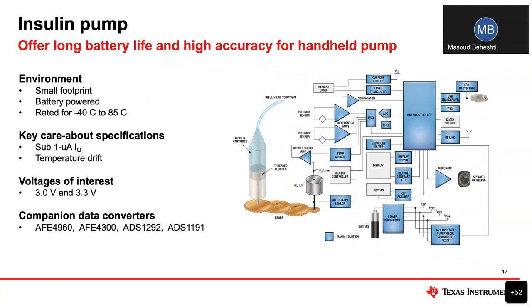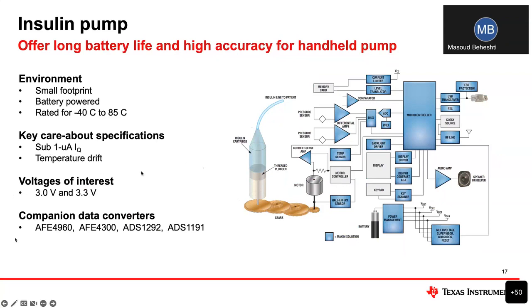Insulin pump is another medical application. You're looking for small footprint — these are typically battery operated and rated for a wider temperature range depending on where the patient is using it. A sub-1 microamp quiescent current is very critical to maximize battery life, and temperature drift is also a key spec designers care about here. Common voltages are 3 and 3.3 volts, used with ADCs such as the AFE4960, 4300, ADS1292, and ADS1191. REF35 pairs well with those devices.